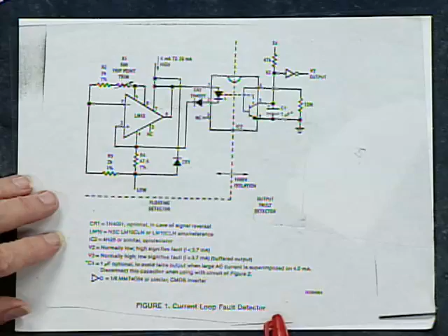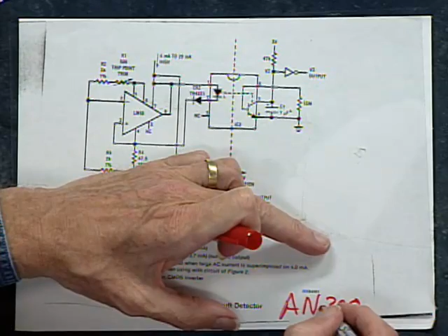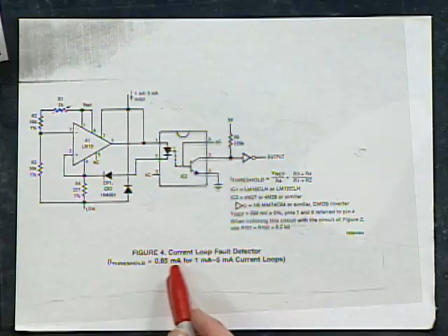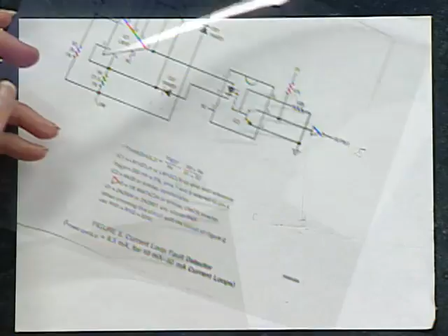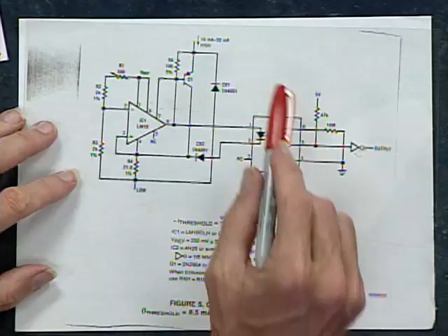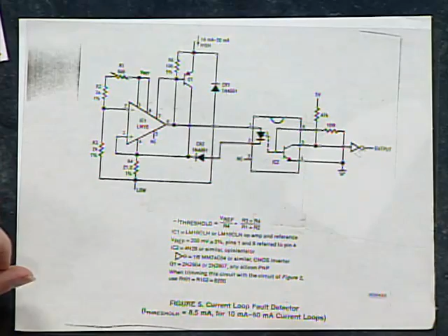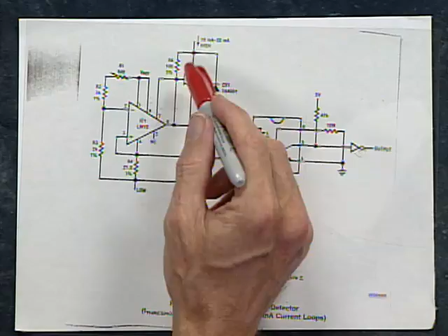So here's a current loop fault detector, and it's in AN300. If you ever need one, it's very valuable. What else do we have? We've got a similar version with a 0.85 milliampere detector for 1 to 5 milliamperes, or an 8.5 milliampere detector. It's a good idea to add a transistor here, because to pull down 50 milliamperes you don't want to ask the LM10 to do it. You want some help from a transistor. So if you ever need to know, is my 4 to 20 milliampere circuit working, a circuit like this may be useful.